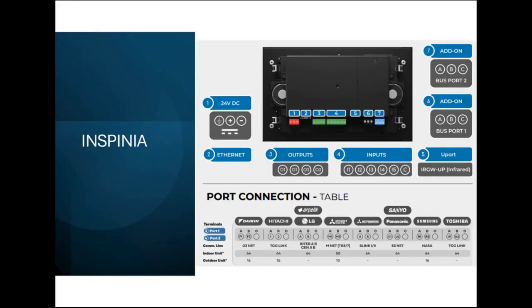And then we have the Inspinia solution completely with screens. As I mentioned before, there are different types of VRF add-on modules. You can use one module in Inspinia screen; there are different types of add-ons for Daikin, Hitachi, LG, Samsung, Toshiba. So it depends on the air condition module you are using in your installation. You can buy one of these add-ons in one port and use iNELS in the other add-on port. Or if it is a 4-inch touchscreen, then there is only one add-on port. So in that case, you can connect to the iNELS system using MQTT. Please make sure that if you are using MQTT, then you need to have an MQTT broker installed in the installation.